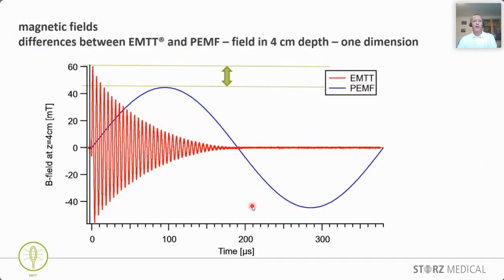It's important to think about where you treat. Normally you do not treat directly on the surface of the body, but typically treat areas below the surface, taking something like 4 centimeters as a first value. An EMTT device, shown here with the red line, reaches maximum 60 millitesla at a field depth of 4 centimeters, where a typical PEMF device is already below that value. So whatever you hear on the market about different strength values, keep in mind you have to look at where you are really treating, not just the surface, where the value might be completely different.